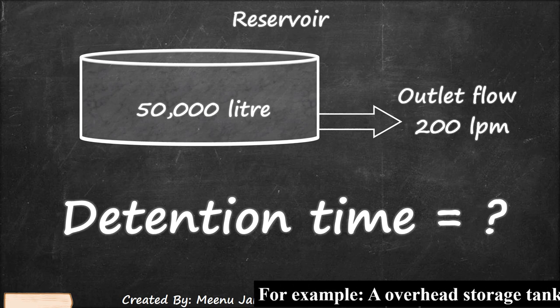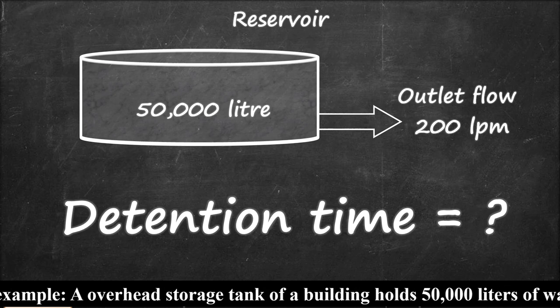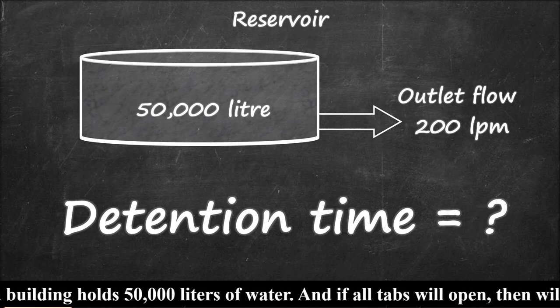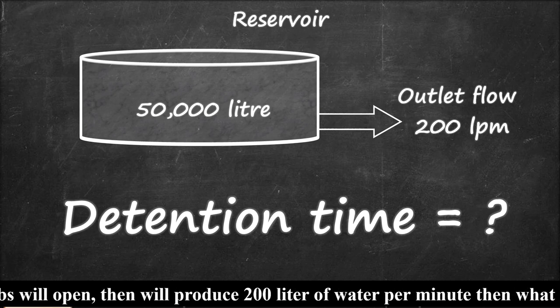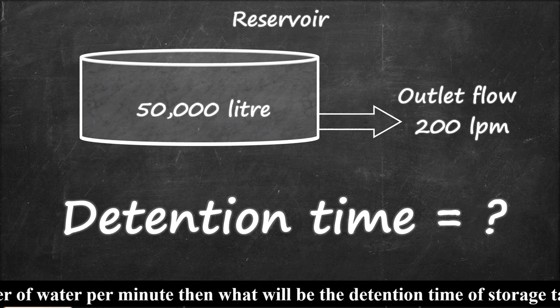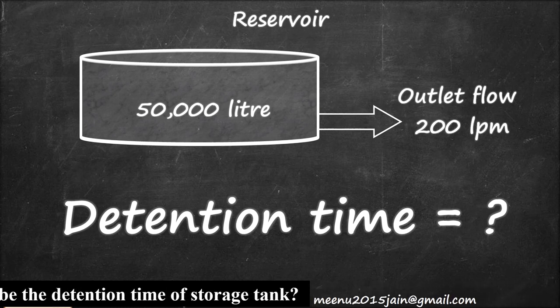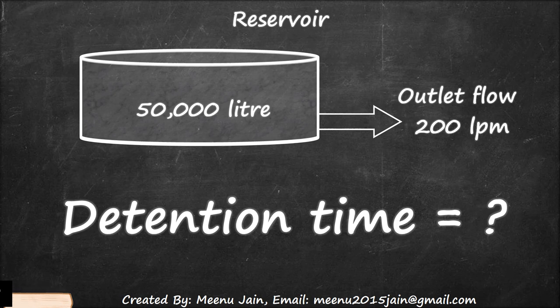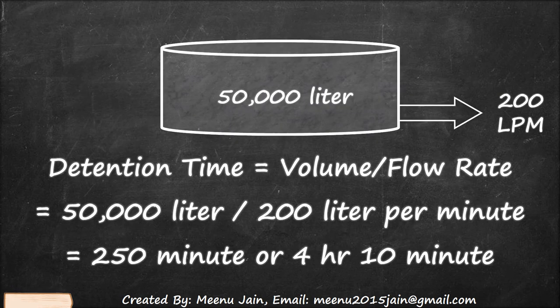For example, an overhead storage tank of a building holds 50,000 liters of water, and if all taps are open, it produces 200 liters of water per minute. What will be the detention time of this storage tank? The formula for detention time is volume divided by flow rate. Volume is 50,000 liters and flow rate is 200 liters per minute, so detention time equals 50,000 divided by 200, which gives 250 minutes, or 4 hours 10 minutes.